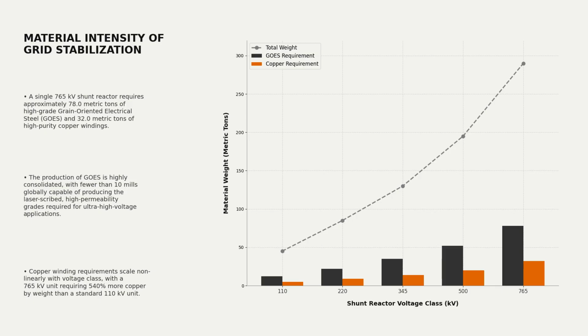The production of this specialized steel is highly consolidated. Fewer than 10 mills globally can produce the grades required to minimize core losses. Copper requirements also scale nonlinearly with voltage. A 765 kilovolt unit requires 540% more copper by weight than a standard 110 kilovolt unit. This high material footprint exposes grid infrastructure directly to base metal supply chain volatility.